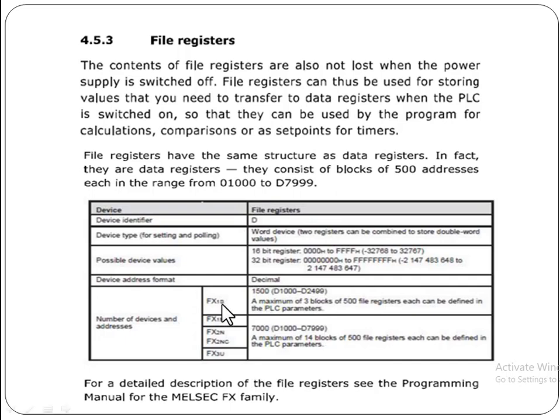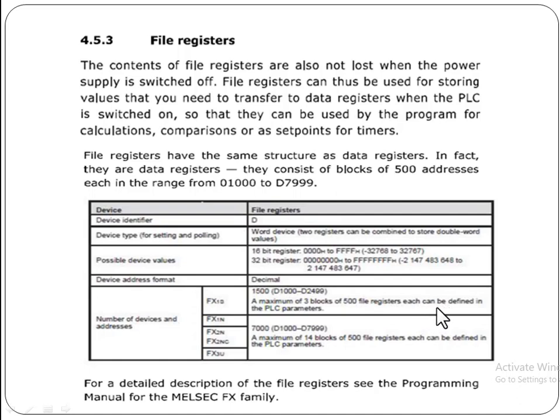For example, FX1S has 1500 file registers, D1000 to D2499, a maximum of three blocks of 500. This number consists of three blocks of 500 file registers, each of which can be defined in the PLC parameters.